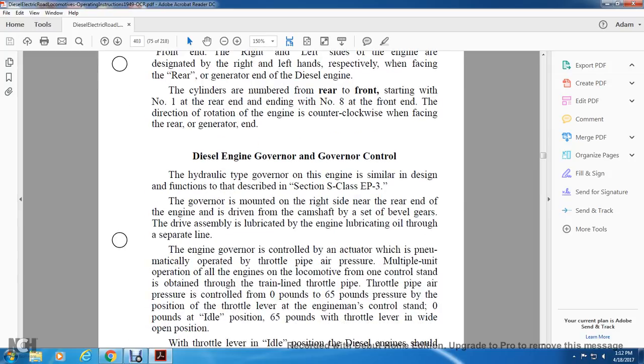Diesel engine governor and governor control. The hydraulic type governor of the engine is similar in design and function to that described in Section S, Class EP3. The governor is mounted on the right side near the rear end of the engine and is driven from the camshaft by a set of bevel gears. The drive assembly is lubricated with engine lubricating oil through a separate line.